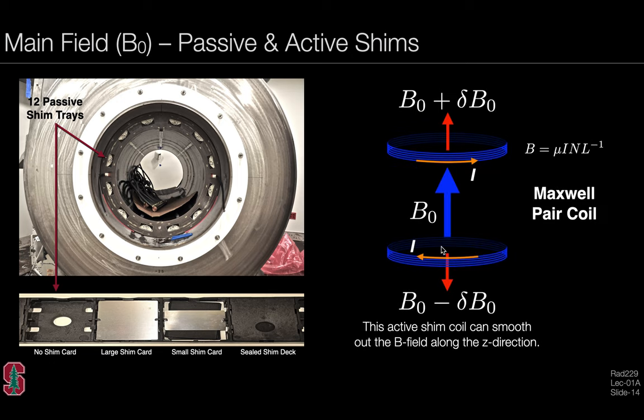Once the system's been installed, it's also possible to perform active shimming to help smooth out the B field along, for example, the Z direction. Here we show a Maxwell pair coil winding at the head and foot of the scanner. By adjusting small amounts of current, we can steer the magnetic field linearity to perhaps improve the overall field homogeneity.